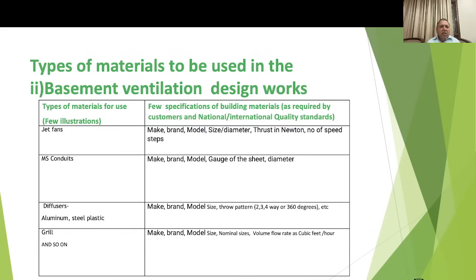For basement ventilation, the main key items are jet fans, MS conduits, diffusers, and grills. For jet fans, specify make, brand, size, diameter, thrust in Newtons, number of speed steps — and a similar concept applies for centrifugal fans. For conduits, specify make, brand, model, gauge of sheet, and diameter.